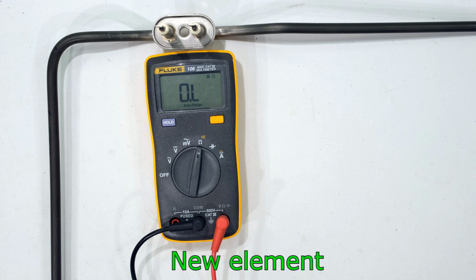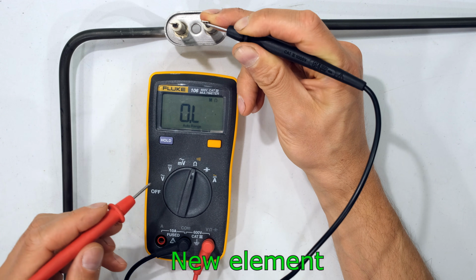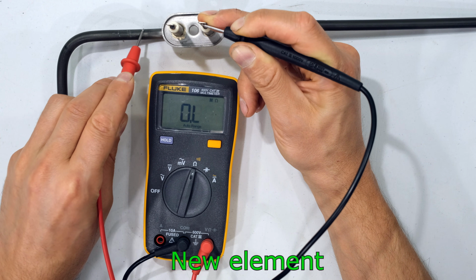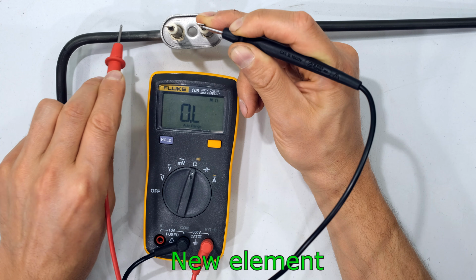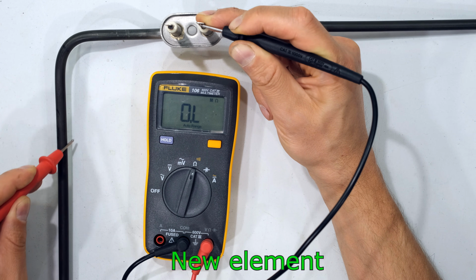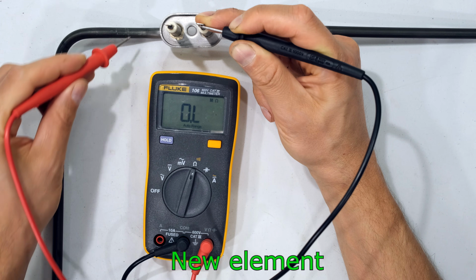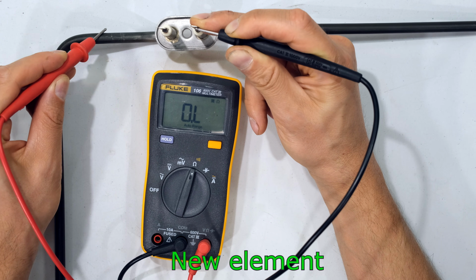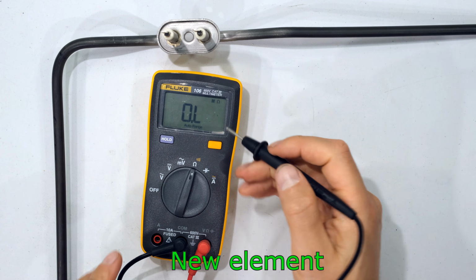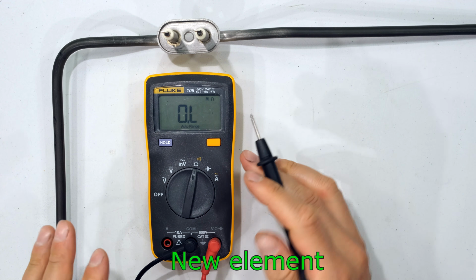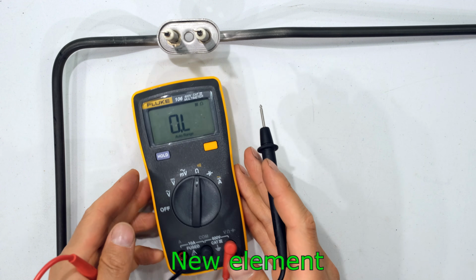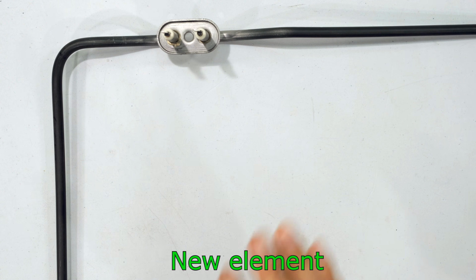And just to show you, if I put my one lead over there and my lead over here, you can see there is no leakage. No current is flowing here, completely isolated. This element is brand new, and therefore, as you can see, I'm not getting a resistance. I should not be getting a resistance, and in this case, I'm not, which is telling me that the element is in good working order.